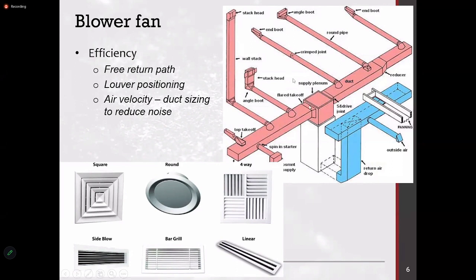Now, in this type of ducting system, you will see certain diffusers which are closer to the unit, closer to the blowing fan, will have very high blow. And when it comes to the longest path, or the most distant diffuser, the airflow will be less. So to ensure equal air is distributed, we call it balancing the air, so that every louver is giving more or less an equal amount of air.